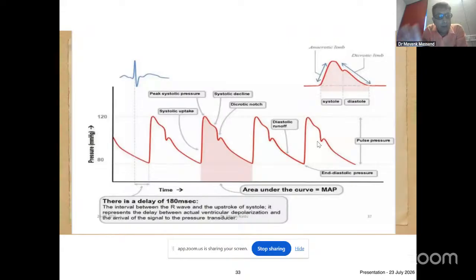Okay. What is the delay? The delay is of 180 milliseconds. First, there is an upstroke, followed by the downstroke. Dicrotic notch is important because this dicrotic notch determines the placement of intra-arterial blood pressure monitoring system. We have to synchronize this particular dicrotic notch if we are employing the intra-arterial blood pressure monitor into 1:1. Otherwise, there will be arrhythmias. After dicrotic notch, there is a downstroke which features that the ventricle is getting empty. Correct?